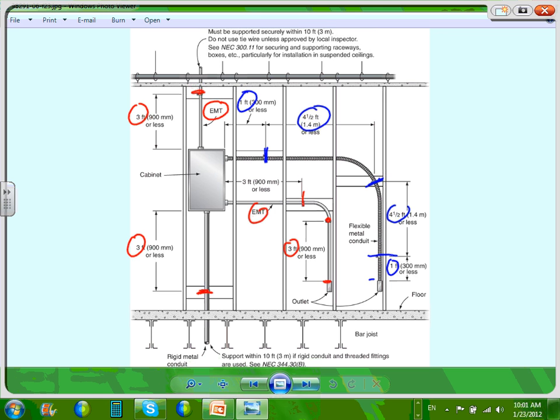So I want to get you to remember 4 numbers. If you have a cable, a foot from the box, you have to support the cable within a foot and at 4.5 feet. If you have a conduit, at 3 feet from the box and 10 feet in between. There's some variation though, but that will cover 80% of the support of cables and conduits.